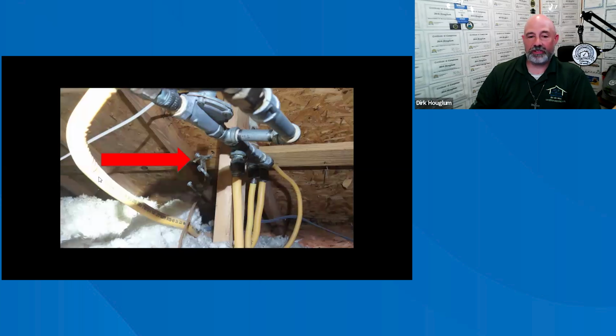And I will see things like this in attics where they actually took that bonding strap off the piping. And we want to see that especially on gas piping with that CSST, the corrugated stainless steel tubing, because it's such a thin material that if it does get hit with electrical current, sometimes it'll actually blow out of there. Or, I mean, an electrical lightning strike could actually blow out of there. So a lot of electricity wants to get out. It wants to get back to its source as fast as possible.